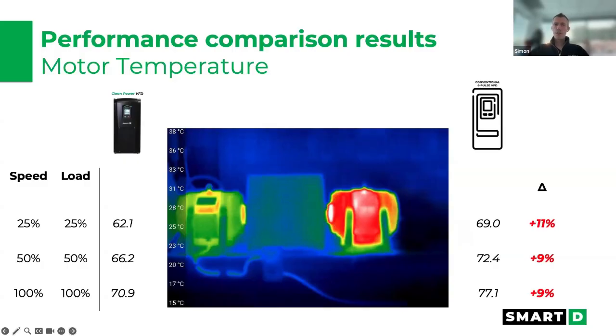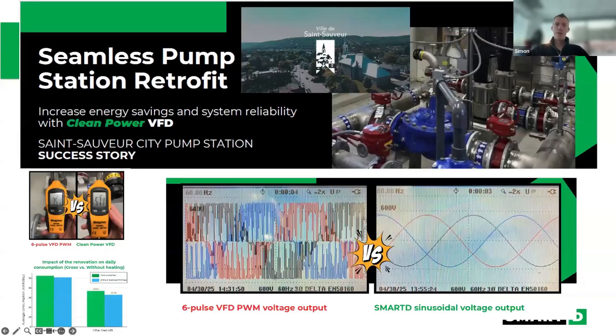So we can monitor this in the lab. You saw Roger's video also shows the sound level. We also see that when we go in the field. This is a retrofit that we did in a pump station in a municipality about 100 kilometers north of our office. And the interesting thing is not only can you see the different signal quality between our drive and another drive just beside it, a standard drive on the other pump. You can see the signal quality, but you can also hear the difference, where in that case, you almost had a 15 dB difference in sound.